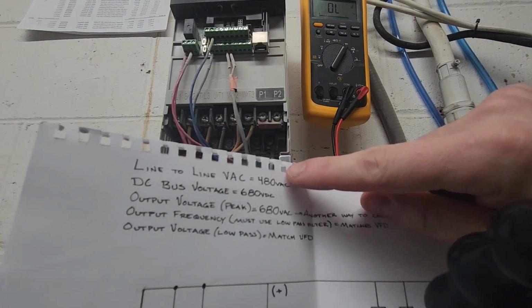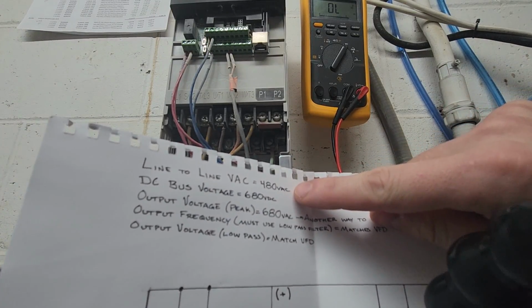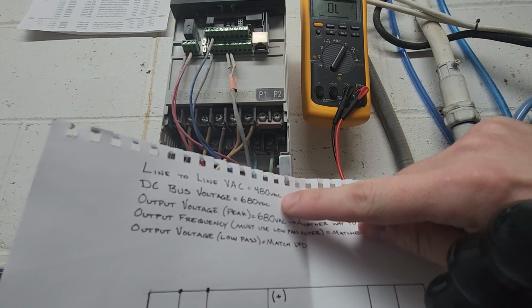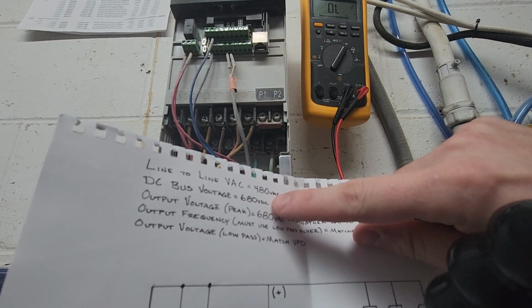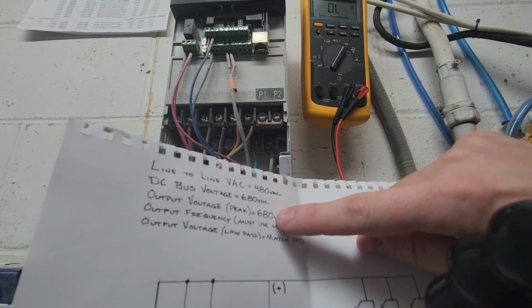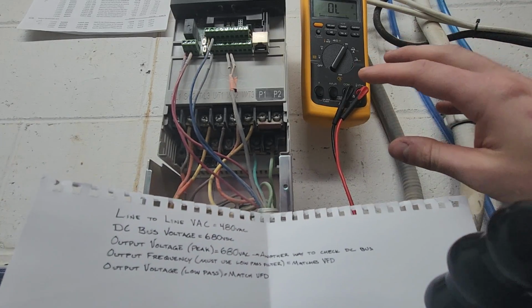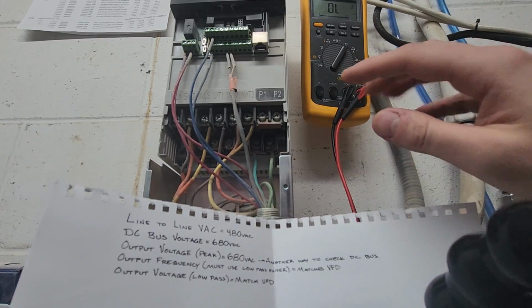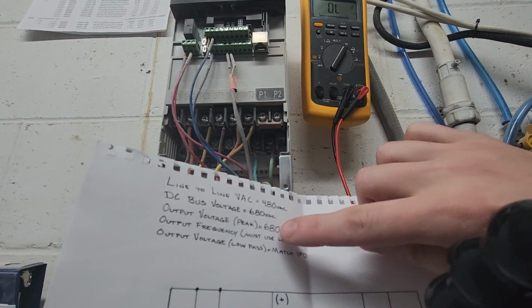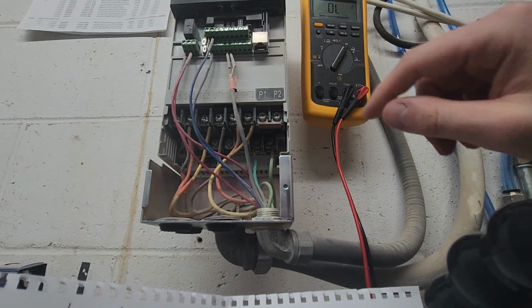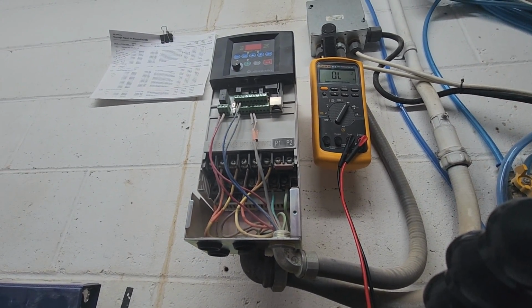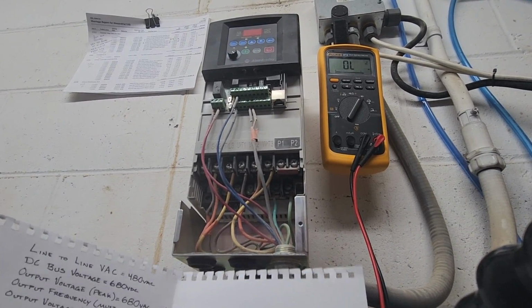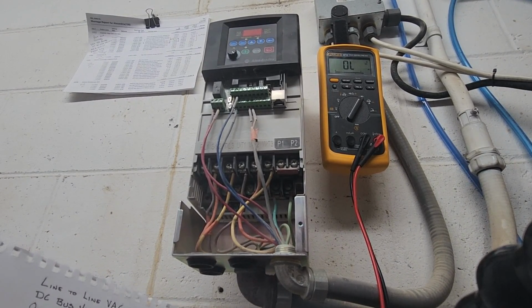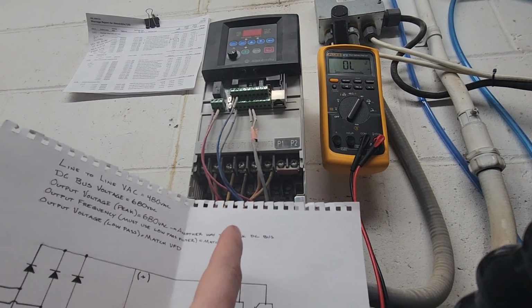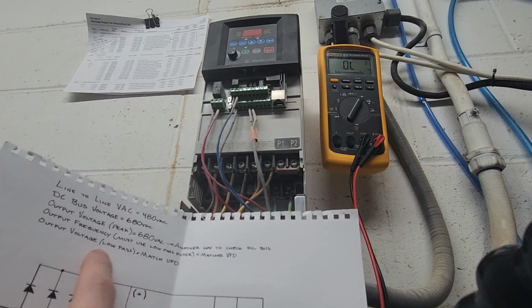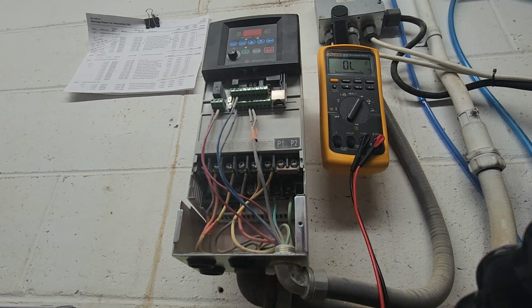So just to review for you guys, you're going to want your line-to-line voltage on your incoming side, 480 volts. Your DC bus voltage, 680. Your output voltage peak without a low pass filter, just raw peak voltage on your output, should be about 680. Your output frequency should match whatever your VFD reads. It's got a readout up here. Again, your frequency reading must be taken with your low pass filter. And then your output voltage should match the VFD as well, and that'll again be with a low pass filter.